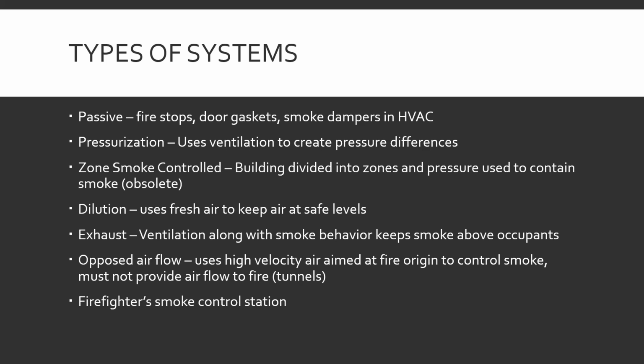Exhaust. Ventilation along with smoke behavior keeps smoke above occupants. Interesting. So yes, in theory, you could be exhausting smoke outside the building. But if it's a really big building, that may not be practical. So all exhaust is trying to do is keep it above people. So let's say it's a big atrium, like at a big hotel. There's multiple floors and it's a big dome and it's all cool. There's a fire in the atrium. What this system will do, since smoke rises, is use ventilation and the fact that smoke rises to try and keep the smoke all the way at the top of the dome. Above the top floor, up by the skylight kind of thing, where down below people can be making their way out and there might be a haze in the air, but the worst of the smoke is out of reach, out of lungs, up there, we've got time kind of thing.